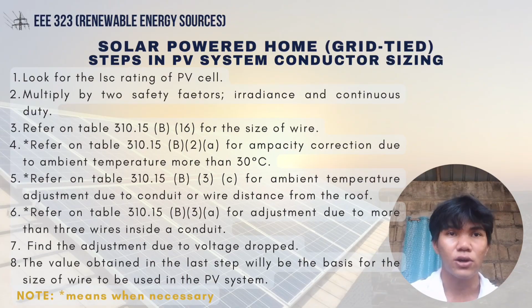Next is to refer to table 310.15 B3C for ambient temperature adjustment due to conduit or wire distance from the roof. For number 6, refer to table 310.15 B3A for adjustment due to more than 3 wires or inside a conduit. Number 7, find the adjustment due to voltage drop.